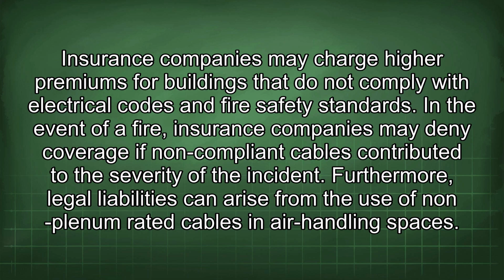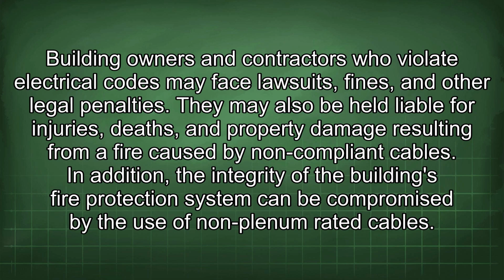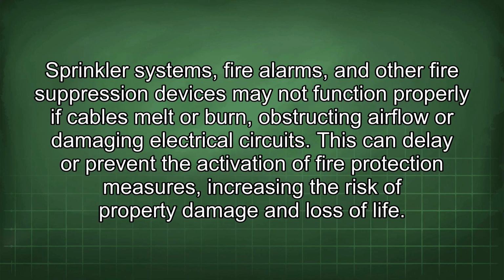incident. Furthermore, legal liabilities can arise from the use of non-plenum rated cables in air handling spaces. Building owners and contractors who violate electrical codes may face lawsuits, fines, and other legal penalties. They may also be held liable for injuries, deaths, and property damage resulting from a fire caused by non-compliant cables. In addition, the integrity of the building's fire protection system can be compromised by the use of non-plenum rated cables. Sprinkler systems, fire alarms, and other fire suppression devices may not function properly if cables melt or burn, obstructing airflow or damaging electrical circuits. This can delay or prevent the activation of fire protection measures, increasing the risk of property damage and loss of life.